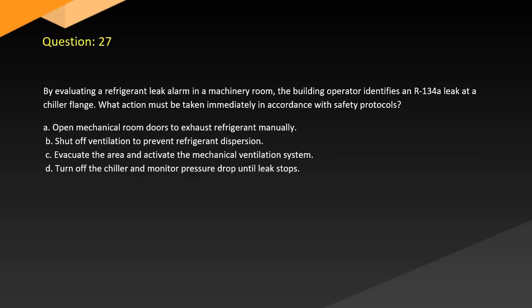Question 27. While evaluating a refrigerant leak alarm in a machinery room, the building operator identifies an R134 leak at a chiller flange. What action must be taken immediately in accordance with safety protocols? A. Open mechanical room doors to exhaust refrigerant manually. B. Shut off ventilation to prevent refrigerant dispersion. C. Evacuate the area and activate the mechanical ventilation system. D. Turn off the chiller and monitor pressure drop until the leak stops.